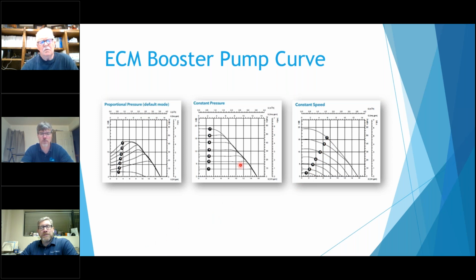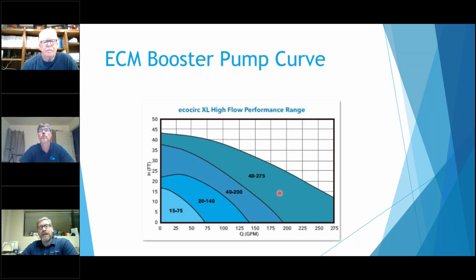Some of the issue with these is it becomes a little bit difficult to figure out where you're operating, especially with these two here, because it's tough to know where they're actually at on that curve. Like this curve 6 here, you could be at 0, or you come out to about 8 GPM, depending on what the system's allowed to do. So it becomes a little bit hard to troubleshoot. And you get to the bigger ones, and these can operate anywhere in these shaded areas. So this 4275 can operate from out here all the way down to here, depending on what speed it's running and all kinds of stuff. So it becomes a little difficult to troubleshoot these pumps with the ECM motors, but they are becoming more prevalent.